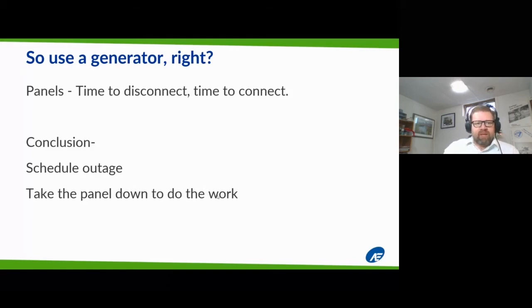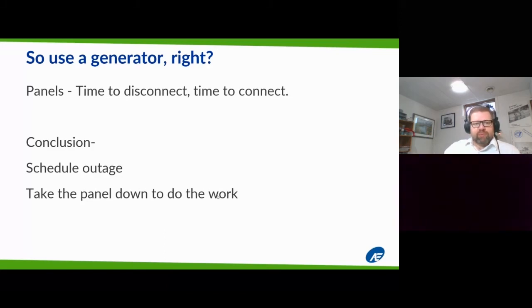A lot of people say, I'll just use a generator. You can totally use a generator to provide power, but the problem is it takes time to disconnect all the cables connected to that equipment, then time to connect those cables from the generator, then you have to turn it on, make sure rotation's correct, and fix surge protectors that popped because someone did something wrong. So between disconnecting and connecting cables, that could be 4 to 8 hours, you could have just done the work instead. If it's a small job under say 4 hours, why even use a generator? Just do the work.